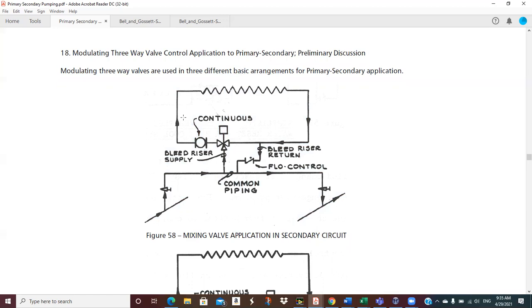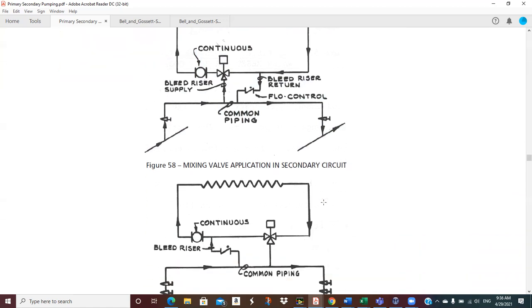pump. We're continuously pumping the secondary. We've got a crossover bridge. We put our three-way valve here to control how much water comes up into the secondary. And we've got our bleed return riser. When we're taking water from the primary into the secondary, we got to bleed some water back out to the crossover bridge that goes back to the return. So then you probably figure out kind of how that operates.